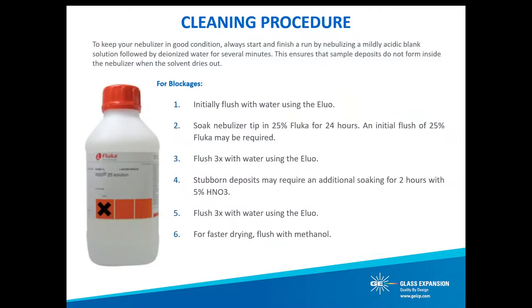So what should you do? Number one rule: always start and finish a run by nebulizing a mildly acidic blank solution, followed by deionized water for several minutes. This helps ensure that sample deposits or crystals do not form on the inside of the nebulizer when the solvent dries out, which can deteriorate performance and shorten nebulizer lifetime. If you let acid or samples run dry in the nebulizer, over time that material deposits on the interior walls — eventually it flakes off and you get a clog. We'll often get a call from a customer saying they were just nebulizing blank solution, but if you're not following a daily cleaning procedure, eventually material coming off the nebulizer or uptake lines will plug the nebulizer.